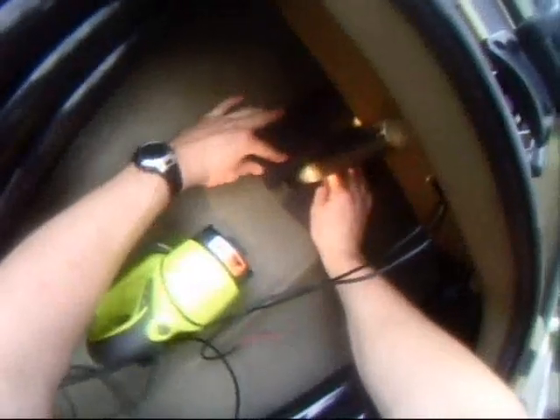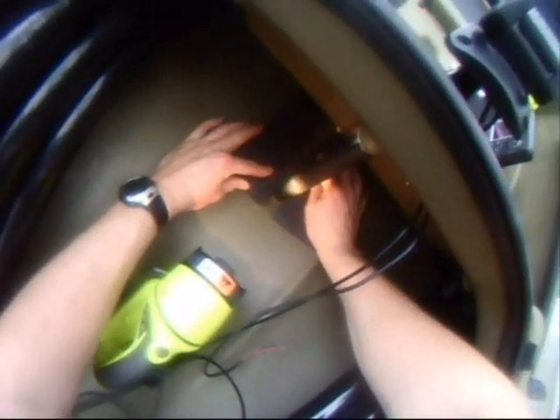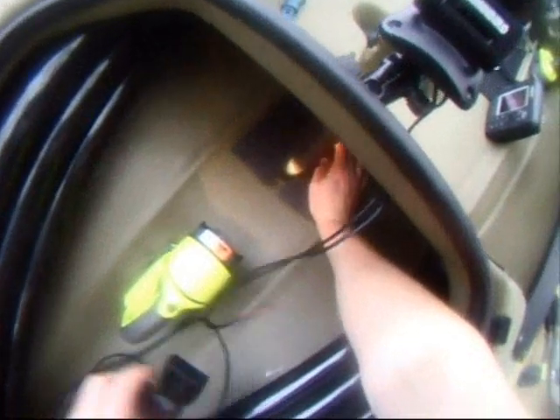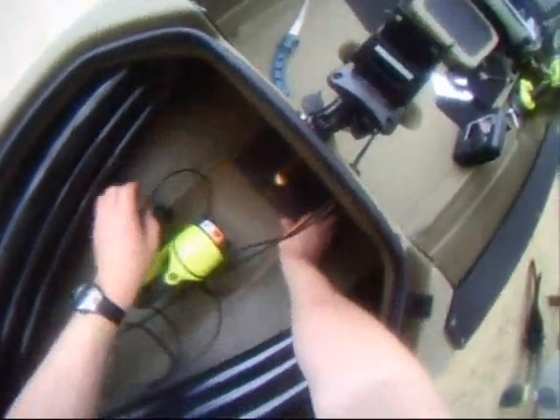Alright, now what I'm doing here is we're fitting the foam block for mounting the transducer. Now, I don't like actually gluing the transducer down. It's very easy to stuff up if you get air bubbles and you won't get a good signal. So what I like to do is I fit a piece of foam to the bottom. I'm fitting the transducer onto the foam there now so I can get the positioning right.